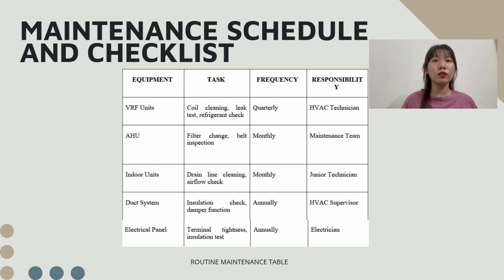The indoor units need drain line cleaning and airflow checks, also on a monthly basis. These are assigned to the junior technicians. The duct system requires insulation checks and damper function testing annually, handled by the HVAC supervisor. Lastly, the electrical panel should undergo terminal tightness and insulation tests annually, and this is the responsibility of the electrician. Following this maintenance schedule helps minimize breakdowns, ensure system efficiency, and extend equipment life.